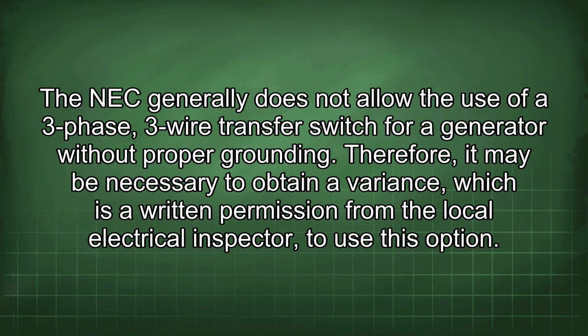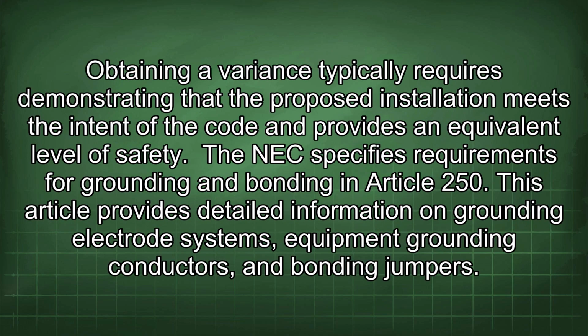The NEC generally does not allow the use of a three-phase, three-wire transfer switch for a generator without proper grounding. Therefore, it may be necessary to obtain a variance, which is a written permission from the local electrical inspector to use this option. Obtaining a variance typically requires demonstrating that the proposed installation meets the intent of the code and provides an equivalent level of safety.